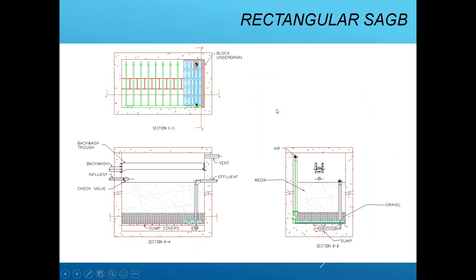This is a rectangular submerged attached growth bioreactor. During a backwash, air and a flow of returned effluent are introduced to clean the media. Solids accumulated in the filter gravity flow into the backwash trough, then gravity feed back to the anoxic tank at the beginning of the system. At the bottom, a system of air lines and block under drain provides a nice, even air flow pattern through the entire reactor.